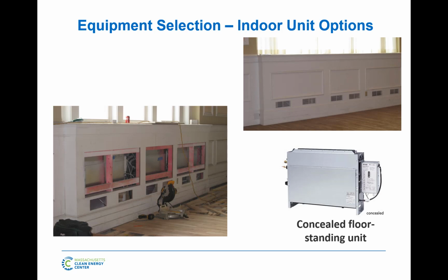This is a ballroom, so you wouldn't really think of a ductless unit for a big ballroom. There's just a lot of these. They actually replaced where the radiators went. So they had radiators all along the exterior wall, and they had this fairly nice looking woodwork to hide it and allow for airflow there. So they ripped out the radiators, used the piping that was left, used the chase that was left by the piping being removed to run refrigerant lines, and fit these right in the same cabinet. And between beginning and end of the project, there's no visual difference on what was happening in the space.